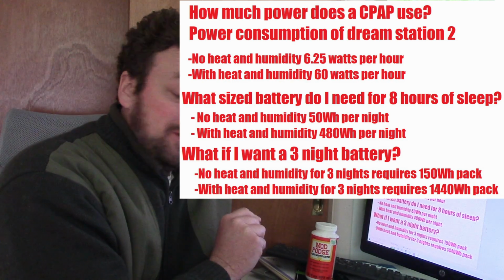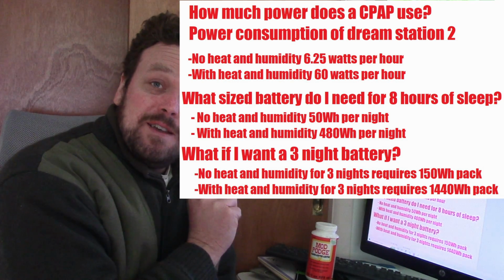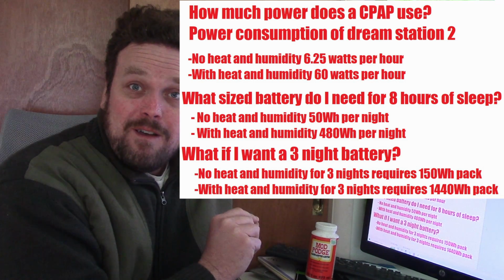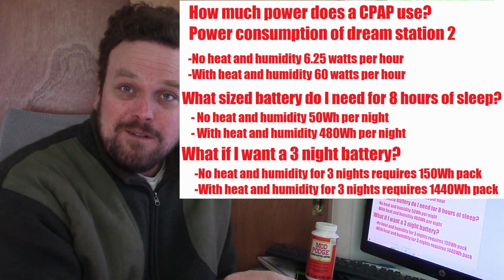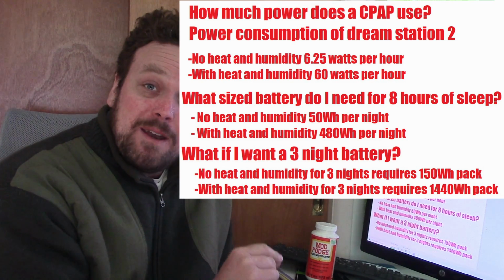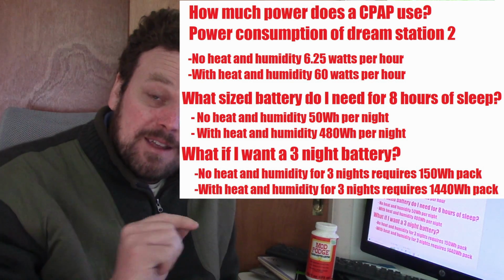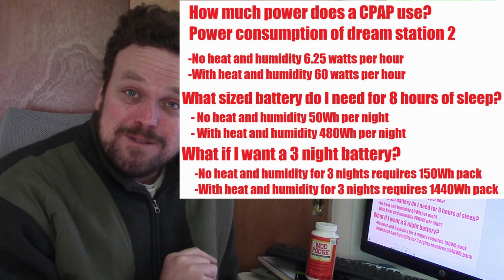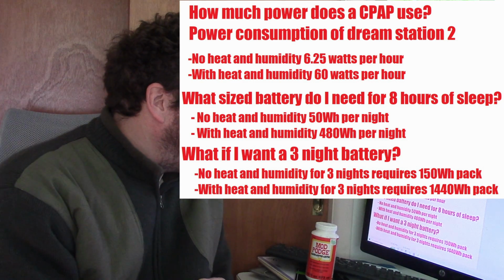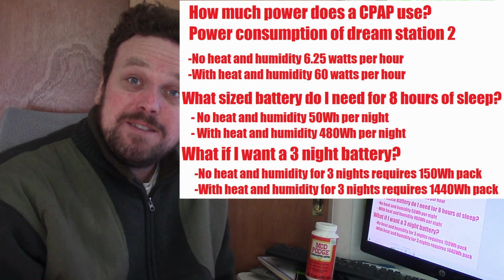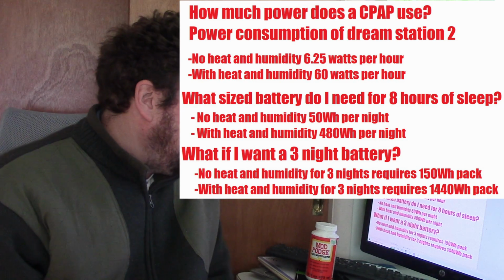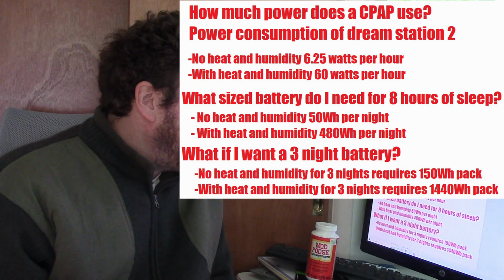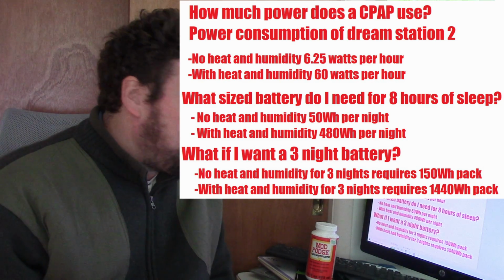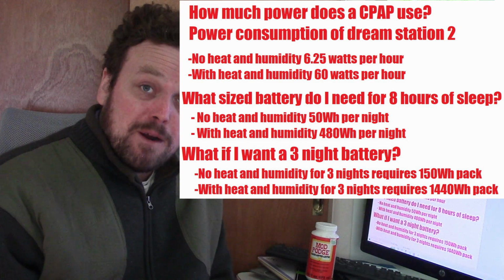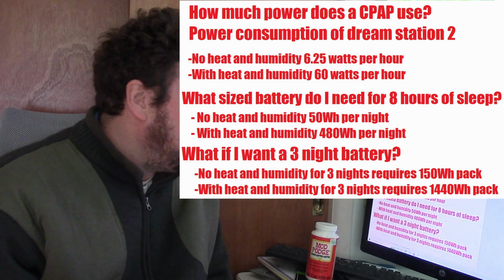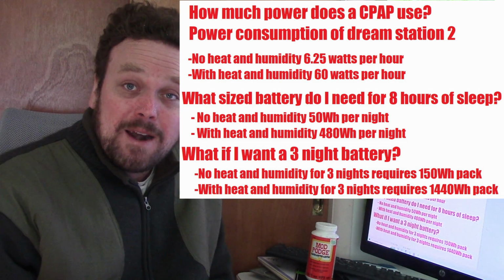So with my DreamStation 2, with no heat and humidity, it used 6¼ watts, or 6¼ watt hours per hour of CPAP use. And with heat and humidity, that number jumped way up to 60 watts, or 60 watt hours per hour of heat and humidity CPAP use. So when you're trying to figure out what size battery you need, let's start with the most basic unit, a single 8-hour night. So the DreamStation 2 with no heat and humidity uses 50 watt hours per night. And when you use it with heat and humidity, it uses 480 watt hours per night.